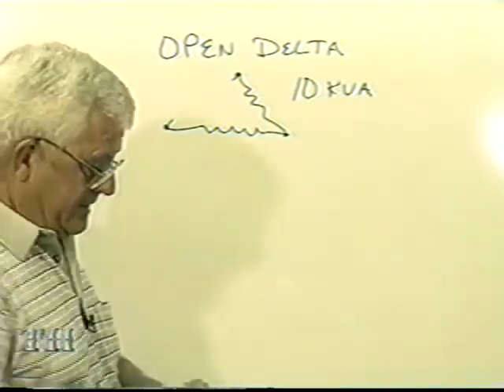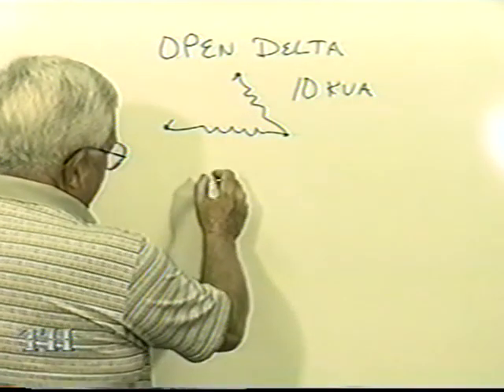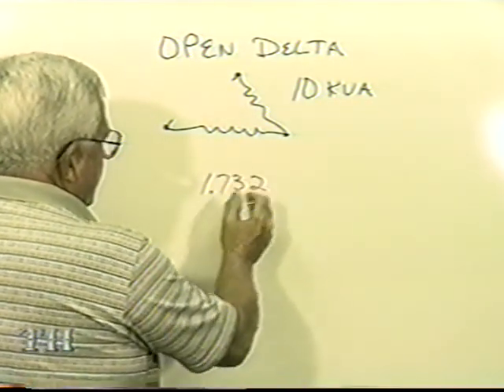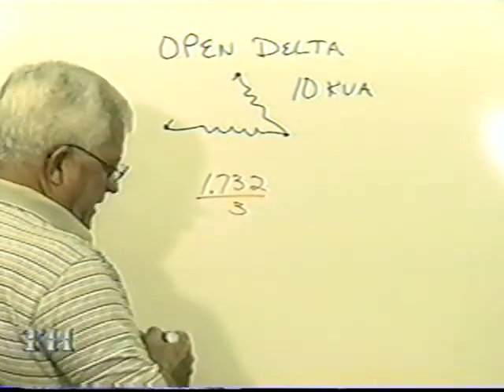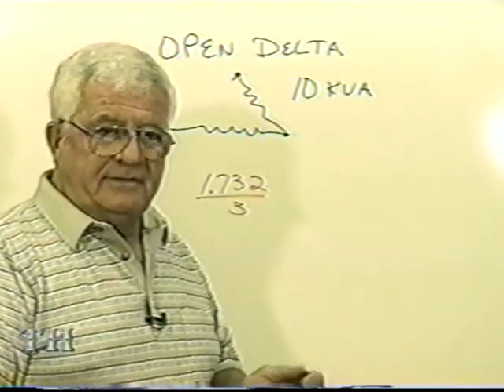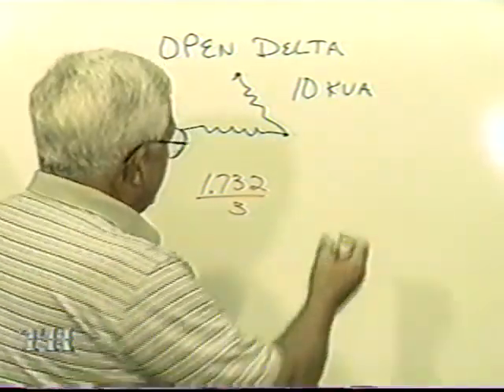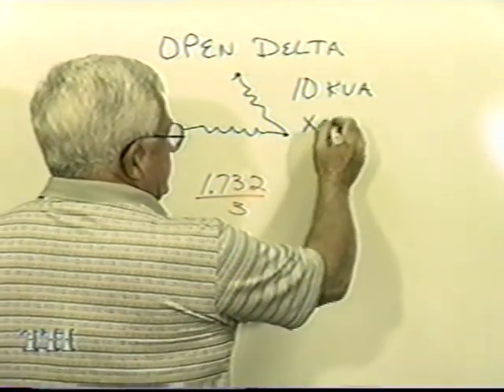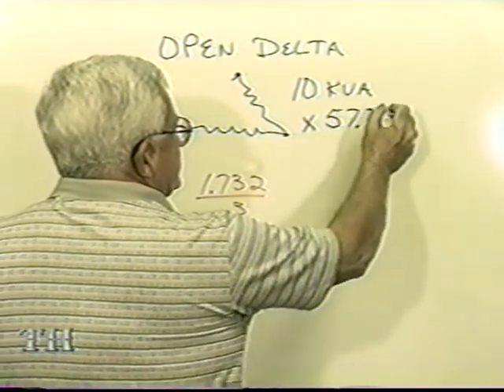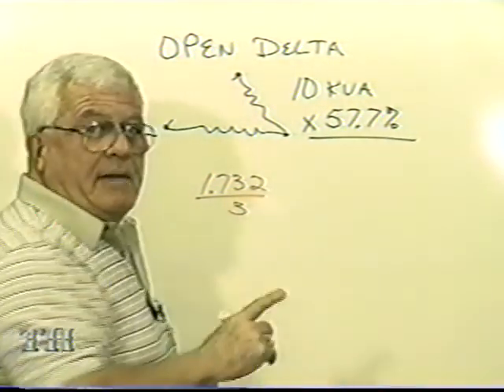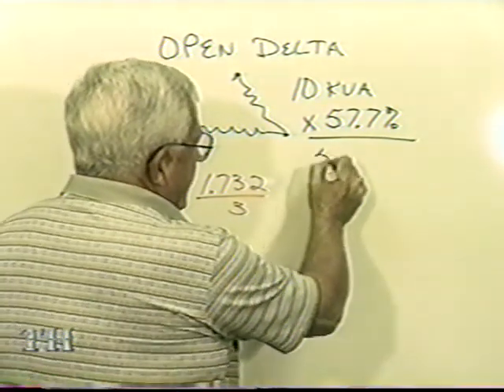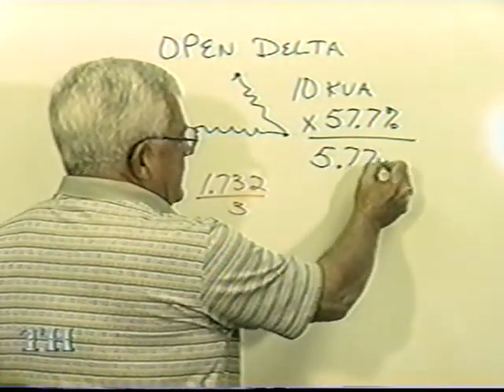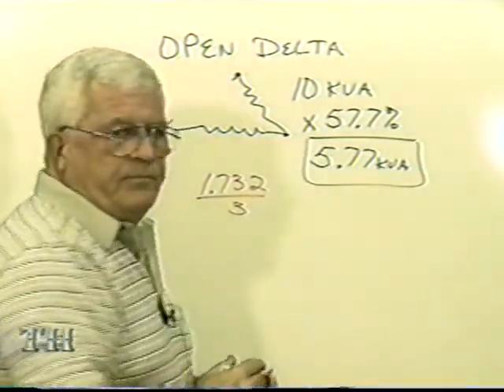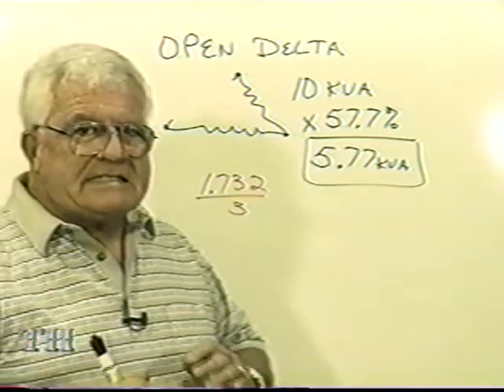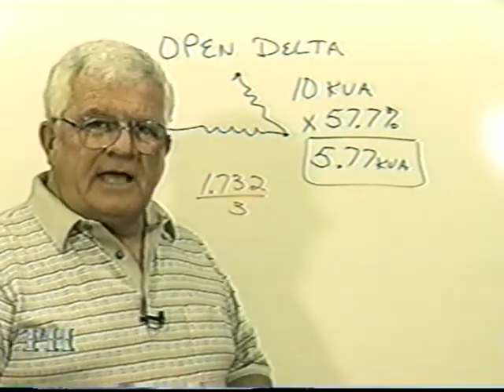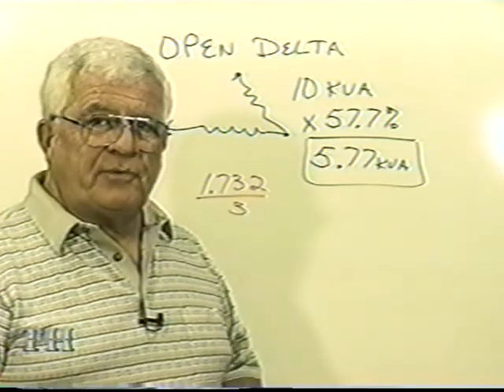Here's how you sacrifice. The number I use is the square root of 3. If you divide that by 3, you're going to come up with 577. That's the magic number for this stuff. If you take this times 57.7%, you could operate open delta at 5.77 kVA, just a little over half. In other words, I can still keep the lights burning, but I'm only going to have about half the power. But I'll still have my 3-phase system.